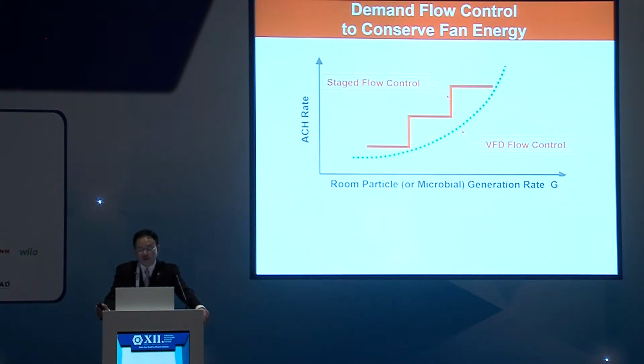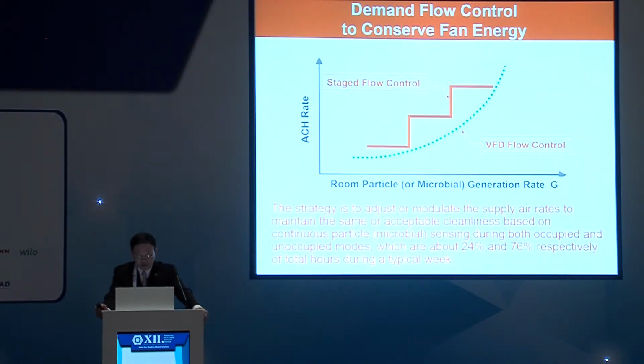Let's say you want to design a clean room for ISO class 5. You have a continuous particle sensor in the room, which is almost like a thermostat, telling you the room particle concentration in terms of air cleanliness 24/7, in real time. And as long as the room is clean enough, you don't need to provide more air than required. So that's the big potential for energy saving. The strategy is to adjust or modulate the supply air rate to maintain the same or acceptable cleanliness based on continuous particle sensing, or sometimes microbial sensing, during both occupied and unoccupied modes. Real occupied time is only about 25% or less. The rest of the time, you can save a lot of energy.